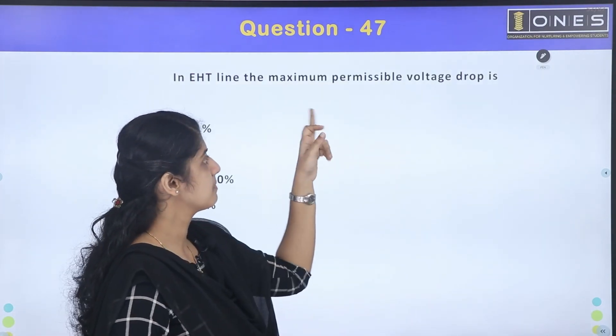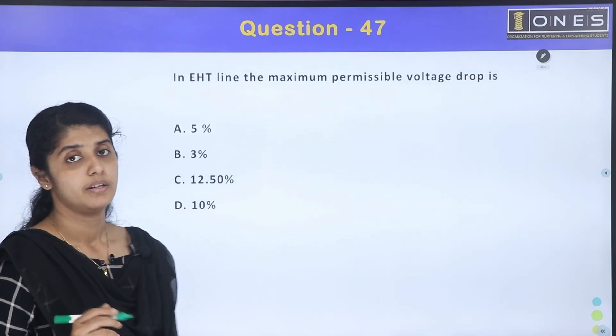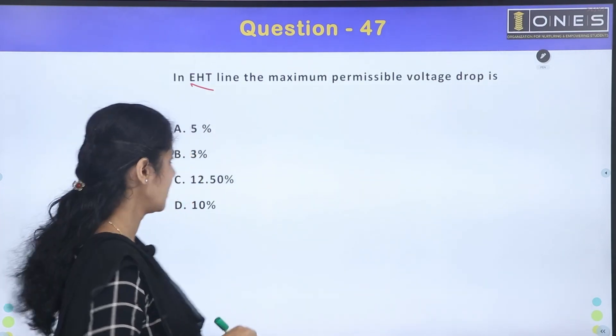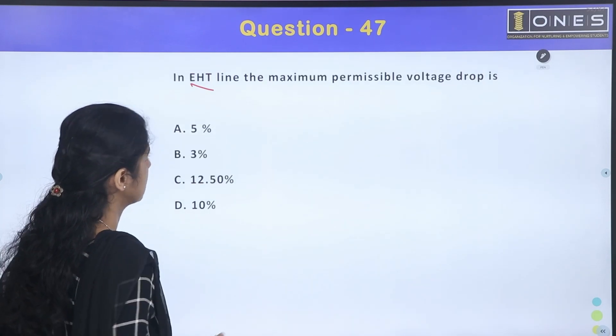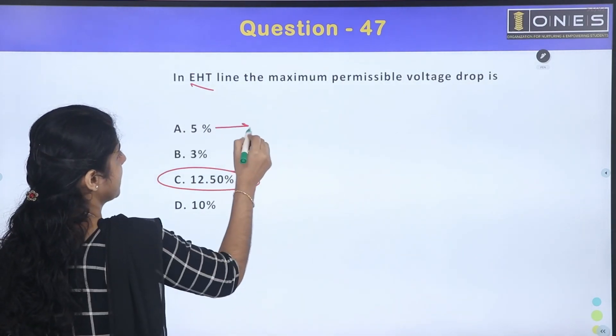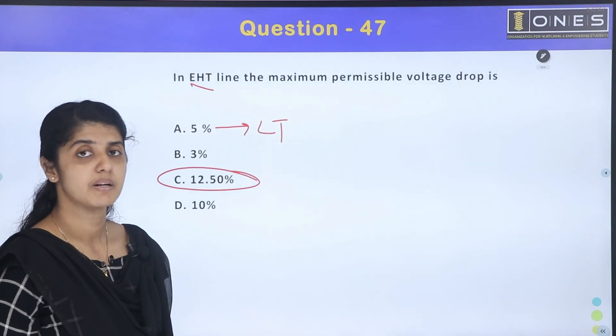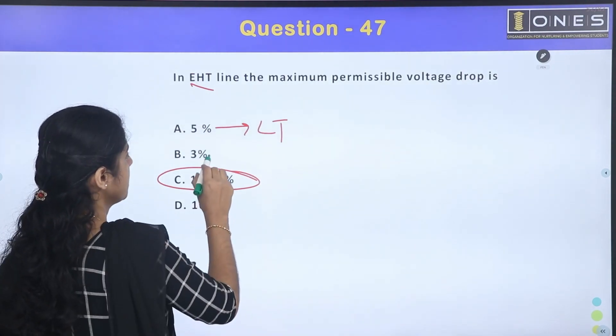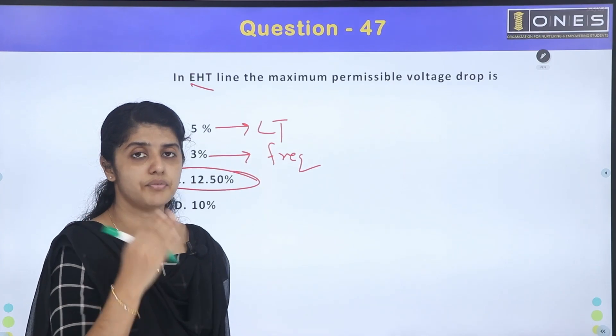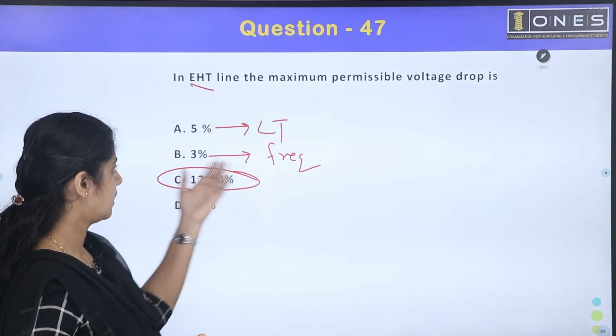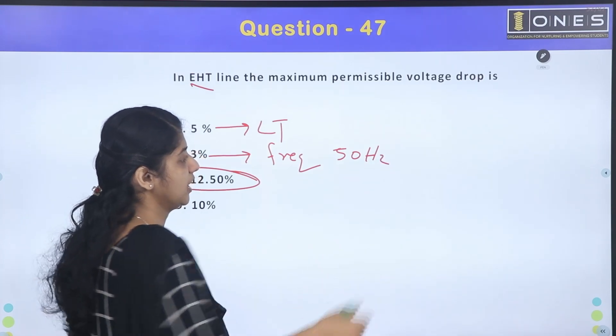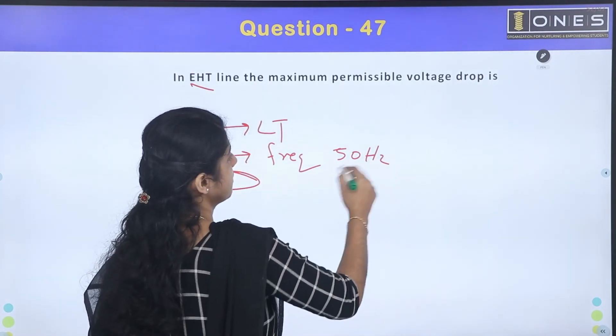In the EHT (Extra High Tension) line, the maximum permissible voltage drop is 12.5%. For low tension lines it is 5%, and for frequency the maximum permissible change is 3%, which at 50 Hz means a variation of plus or minus 1.5 Hz.